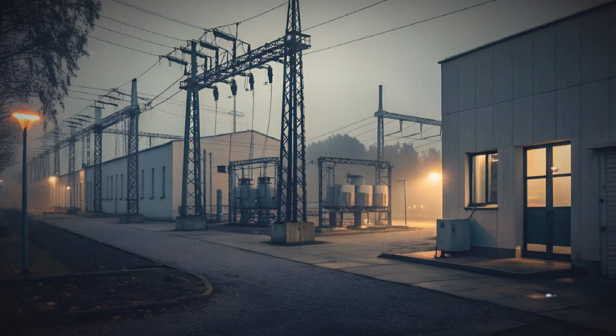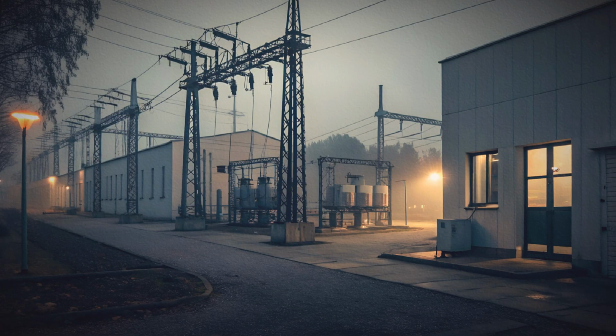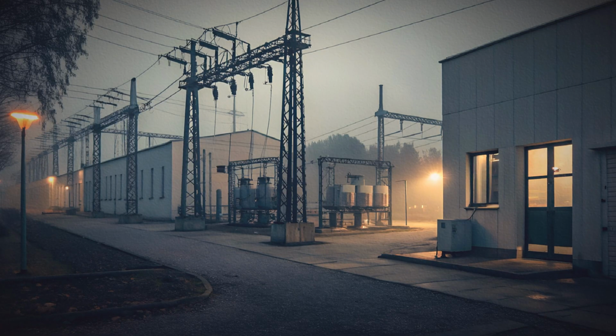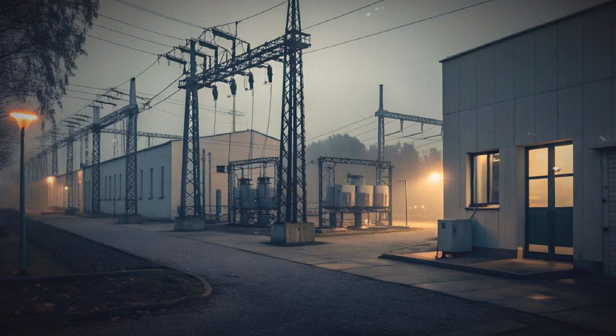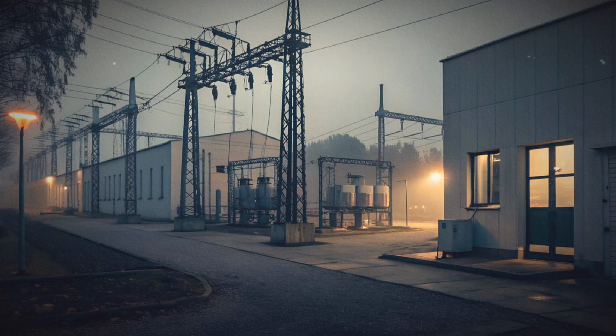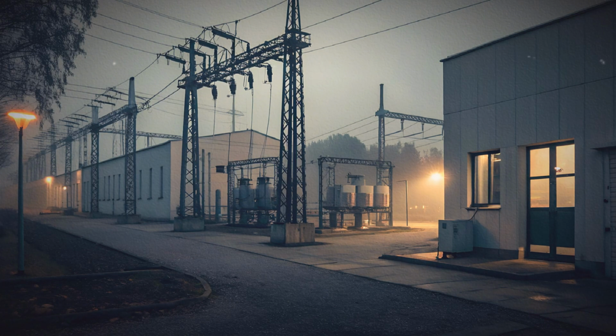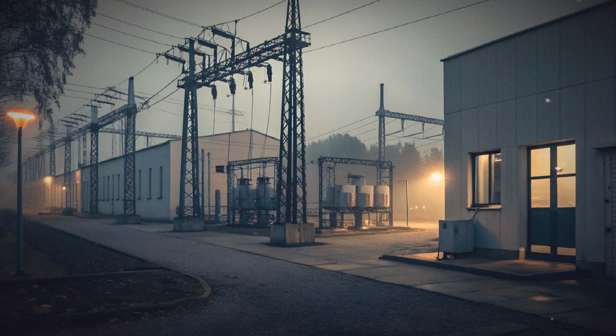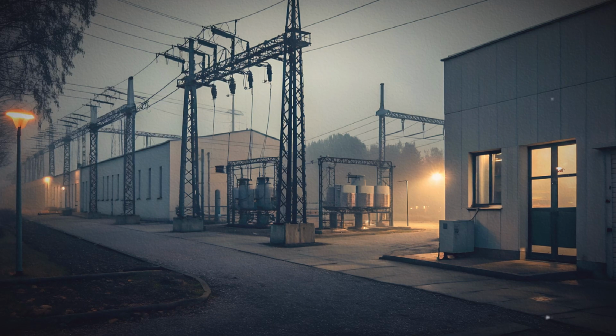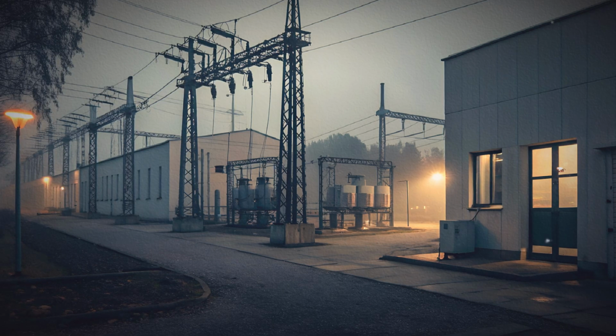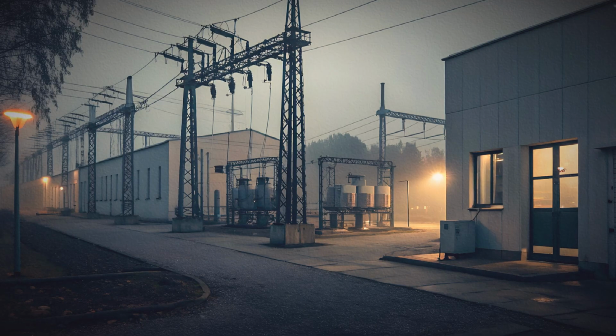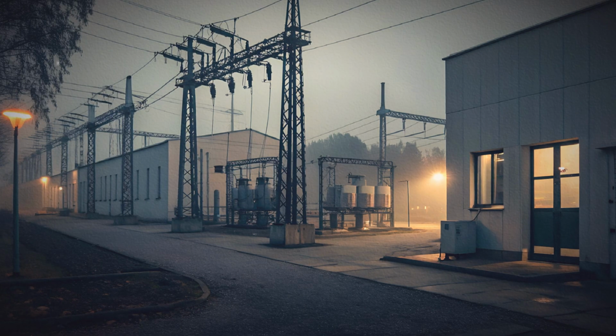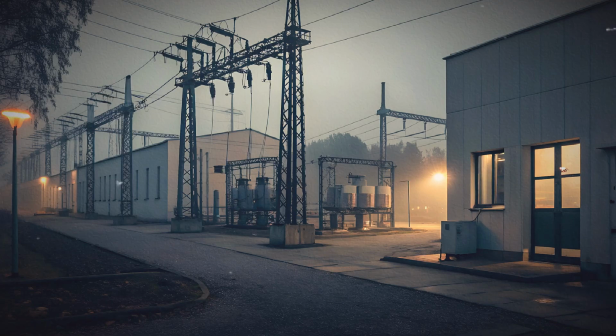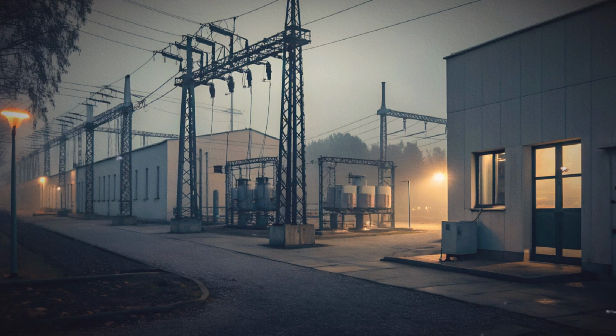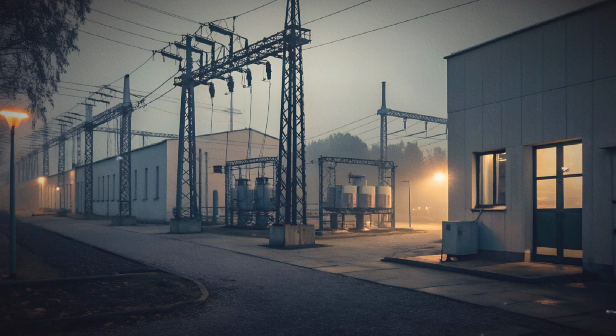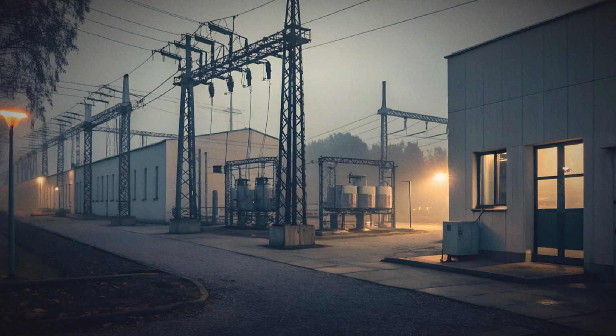In operation, a substation performs a sequence of tasks repeatedly. It receives power at one voltage. It measures currents and voltages. It adjusts voltage levels as needed. It provides switching and protective actions when necessary. It communicates status to control centers. It facilitates distribution to local feeders. These functions together make substations critical nodes in the larger electrical grid.